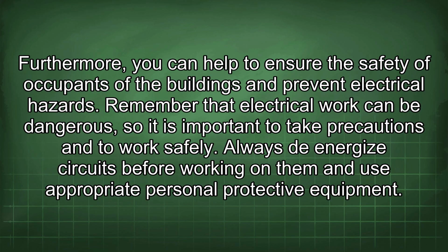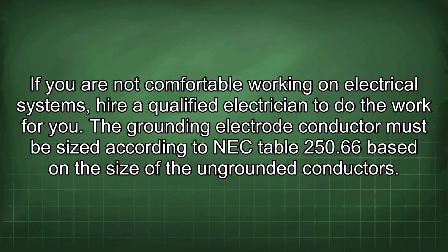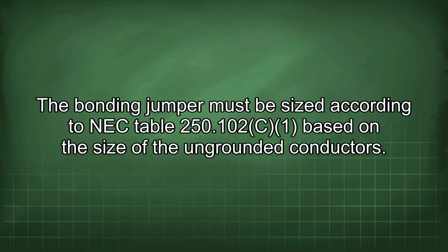Remember that electrical work can be dangerous, so it is important to take precautions and to work safely. Always de-energize circuits before working on them and use appropriate personal protective equipment. If you are not comfortable working on electrical systems, hire a qualified electrician to do the work for you. The grounding electrode conductor must be sized according to NEC Table 250.66 based on the size of the ungrounded conductors. The bonding jumper must be sized according to NEC Table 250.102 based on the size of the ungrounded conductors.